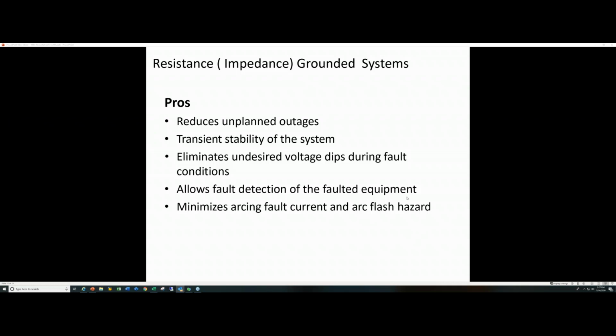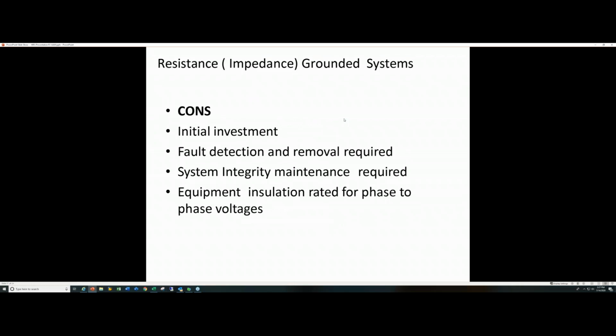It also allows for fault detection of the faulted equipment. What do I mean by that? I'll tell you about that in just a second. And it minimizes arcing current. So your arc flash hazard is reduced significantly. What are some of the cons?